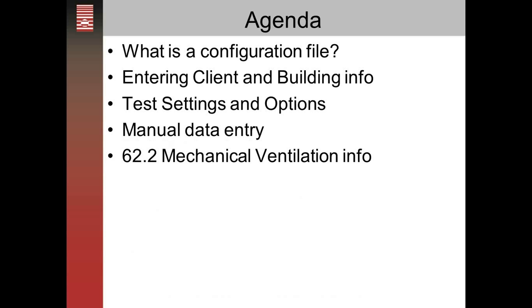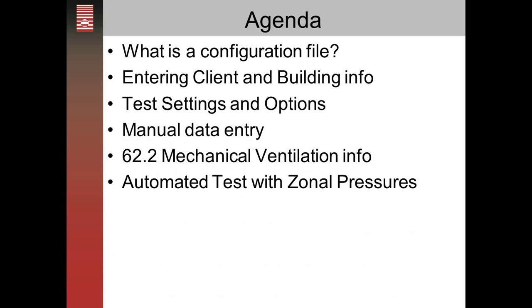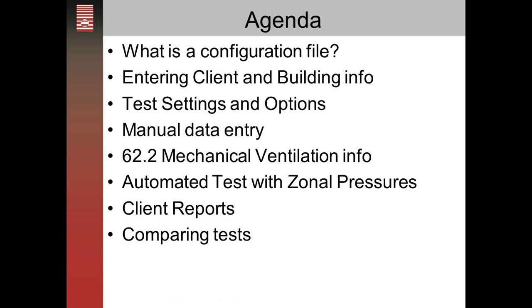We'll go over in some detail the ASHRAE 62.2 ventilation information you'll be entering and how that calculates results. We'll also be demonstrating an automated test using zonal pressure diagnostics, so you can measure attic pressure and garage pressure and have that included in the data. Then we'll go over the reports in some detail — what they look like. Tektite also has the option of comparing tests, bringing up a pre-test and a post-test before and after work was done on the building, and it'll show the CFM change from pre-test to post-test.